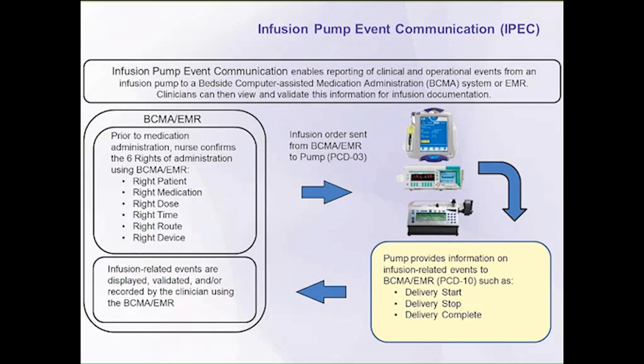Infusion pump event communication, while it works best with PIV, the previous profile, it can also be run independently. It essentially logs all the events that take place during the course of a medication administration. So if there's a start of delivery, somewhere along the line it gets paused or stopped, or at the completion of the delivery, all of that information can be logged.